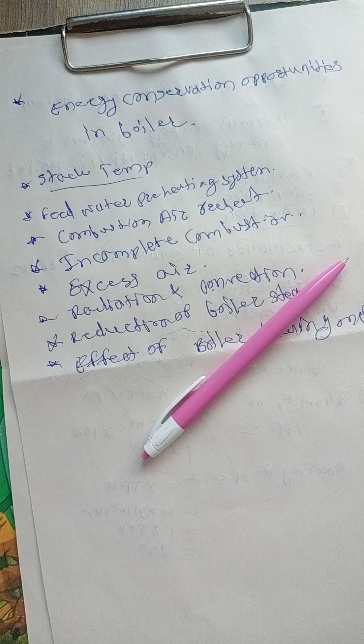At zero output, the efficiency of the boiler is zero and any fuel fired is used only to supply the losses. As the load falls, so does the mass flow rate of gas through the tubes. Below half load, most combustion appliances need more excess air to burn the fuel completely. In general, the efficiency of the boiler reduces significantly below 25% of the rated load, and as far as possible, operation of the boiler below this level should be avoided.